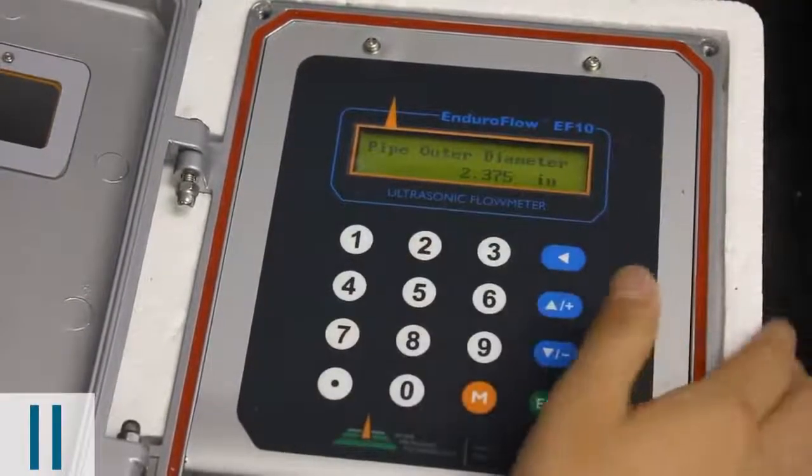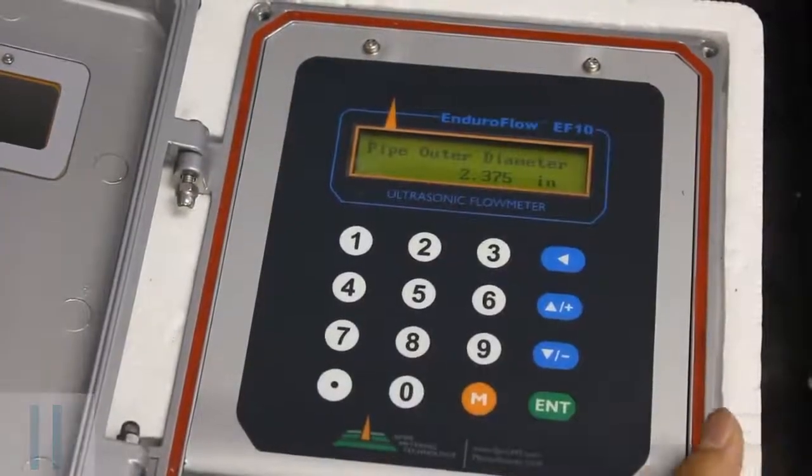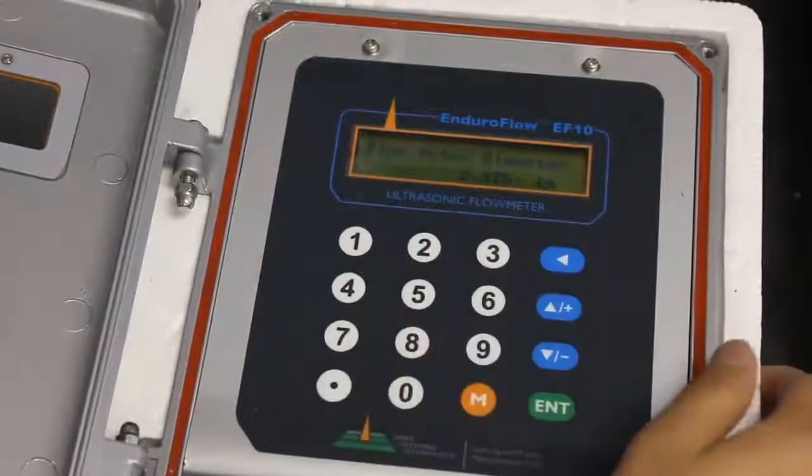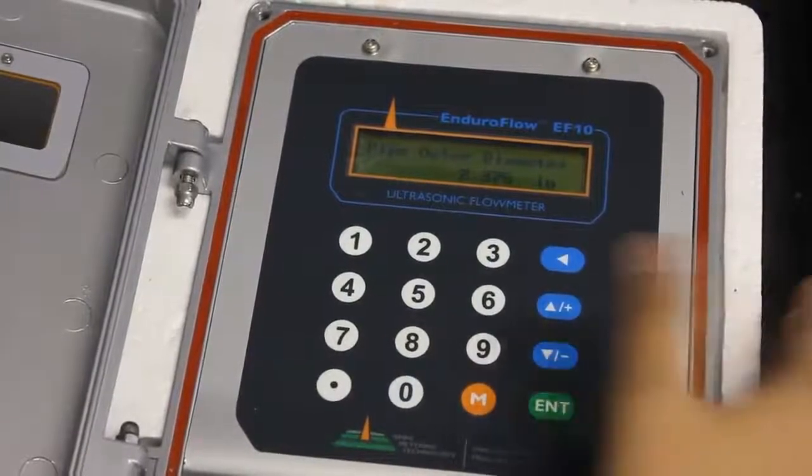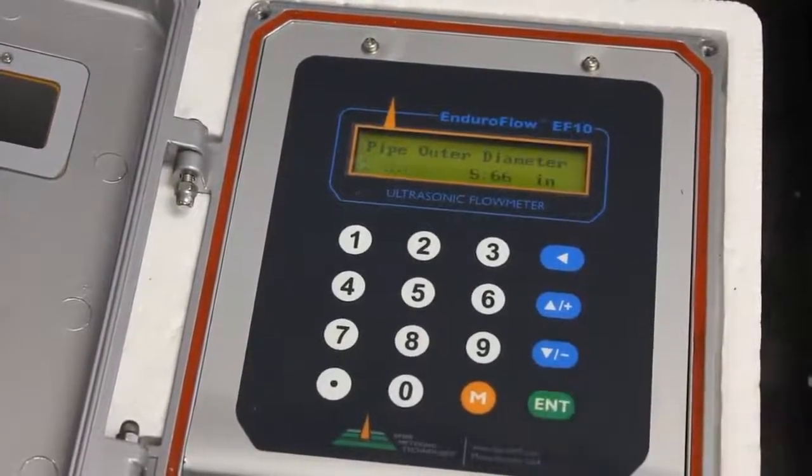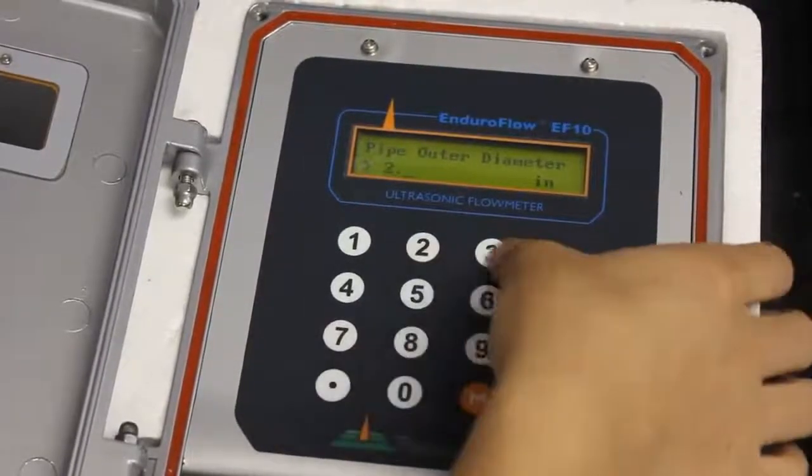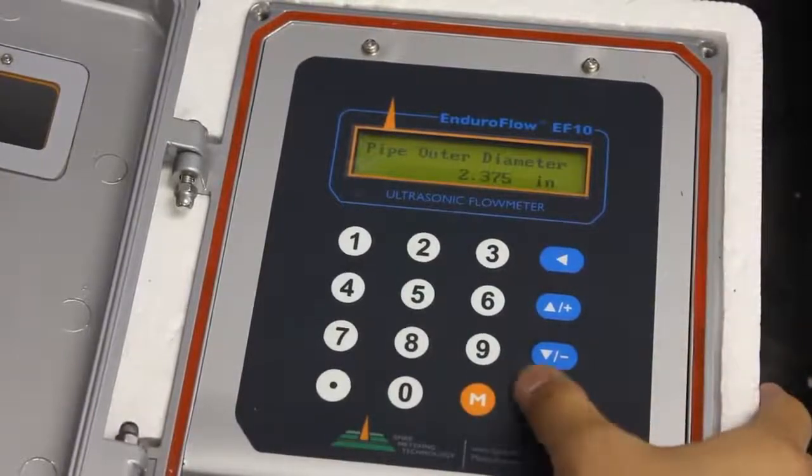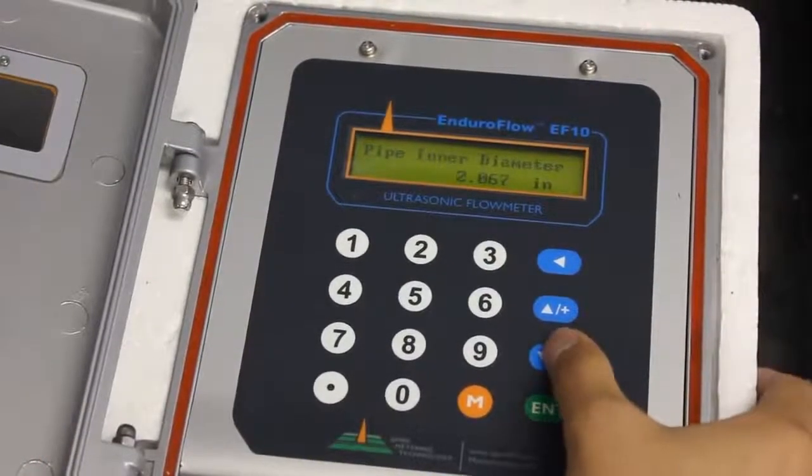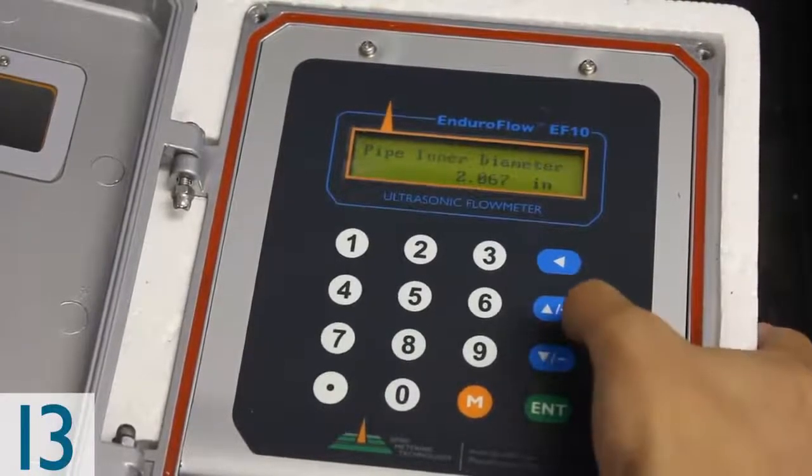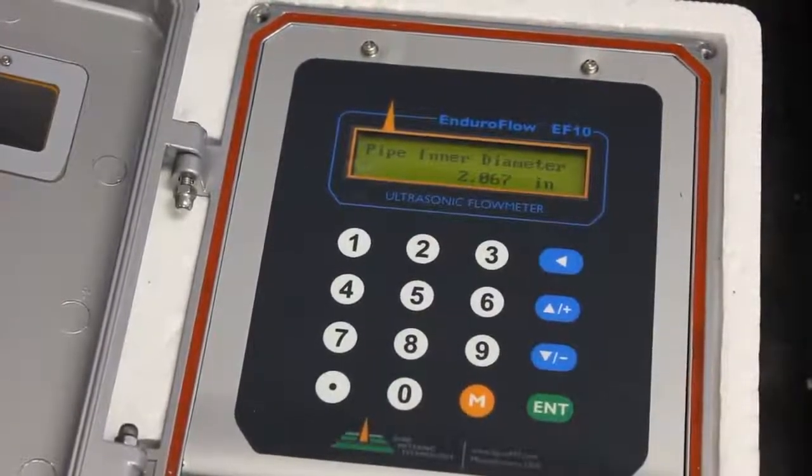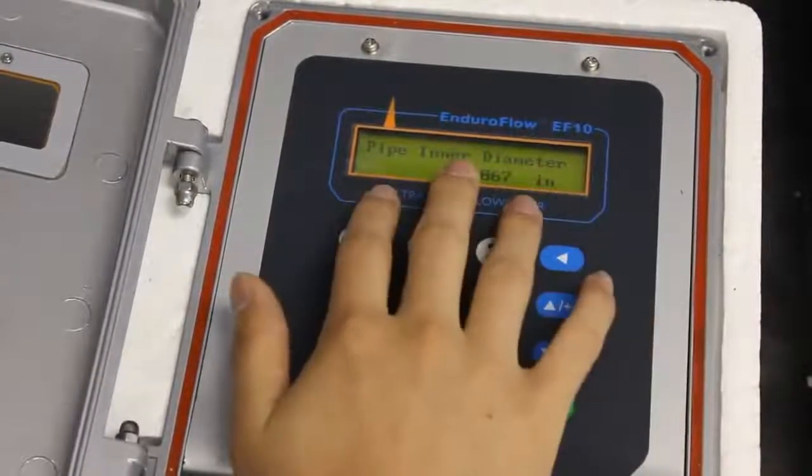Now we go to menu 11 and this is the part where we set up the pipe parameters. Menu 11 is the pipe outer diameter. Make sure you know this. Today we're using 2.375 inches. Say we were using 5, you just press enter, 5. Say it was 5.6, 6, enter. But we're using 2.375. Next we go to menu 12 to set the pipe thickness, 0.154. Next is menu 13. You can scroll between menus by up and down here, by these arrows. Menu 13, the inner diameter is automatically calculated based on your outer diameter and your wall thickness. So you don't actually need to enter anything here.